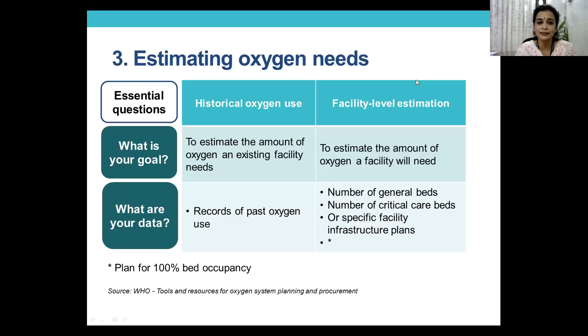But what you need to remember is you have to plan for 100% occupancy. The mistake that people often make is you calculate 100%, then you build up your system saying, I have only 50 to 60% occupancy or 35 to 45% occupancy. That's the problem, why we have situations like this happening today. So what you plan, 100% peak load, that is what you need to develop as a system for the oxygen needs of your hospital.